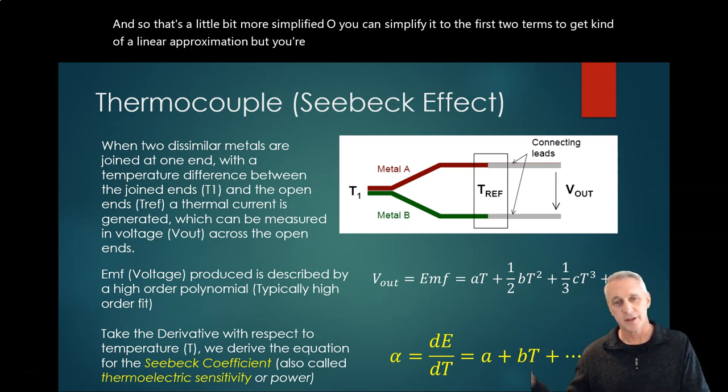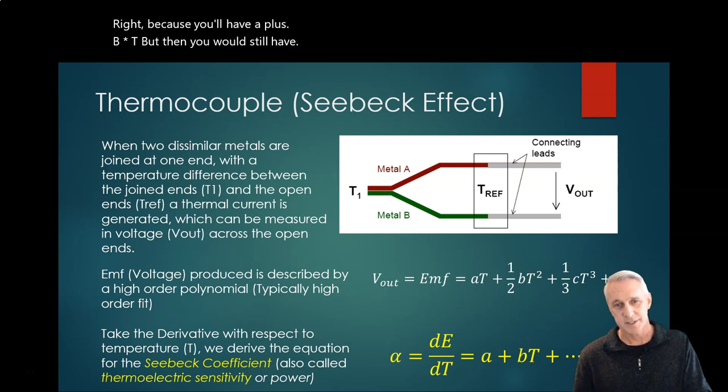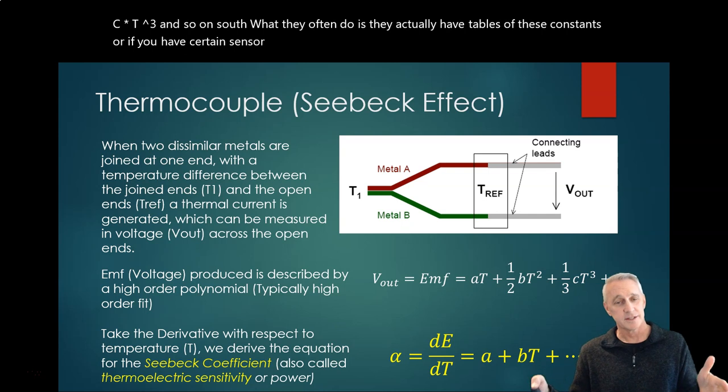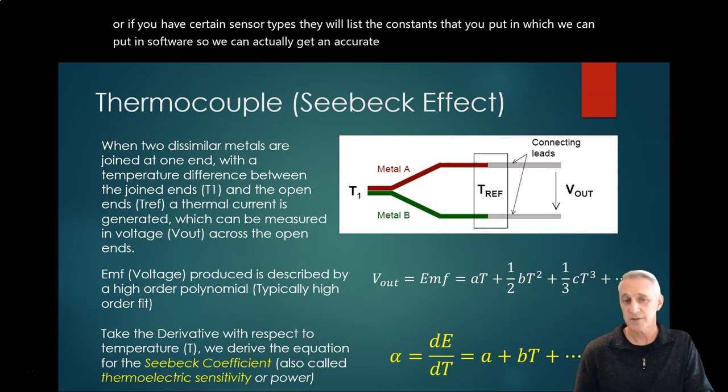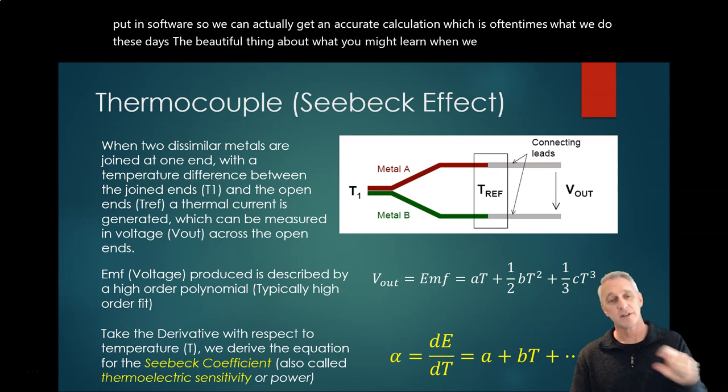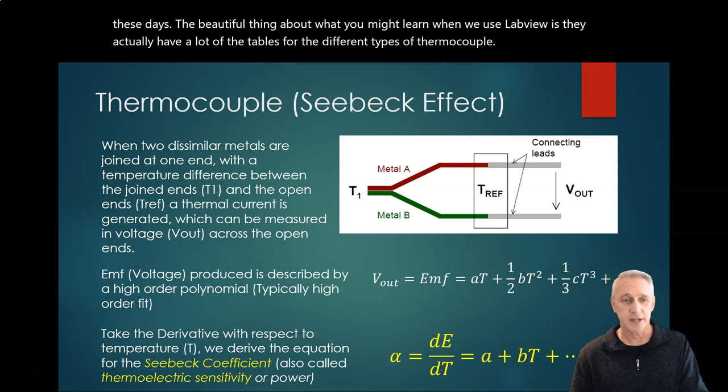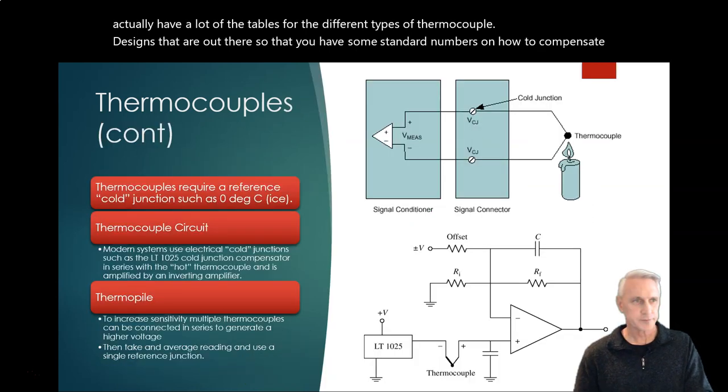You can simplify it to the first two terms to get kind of a linear approximation, but you're really missing the boat on all the other terms because you'll have A plus B times T, but then you would still have C times T squared and so on. So what they often do is they actually have tables of these constants. Or if you have certain sensor types, they will list the constants that you put in, which we can put in in software so we can actually get an accurate calculation, which is oftentimes what we do these days.